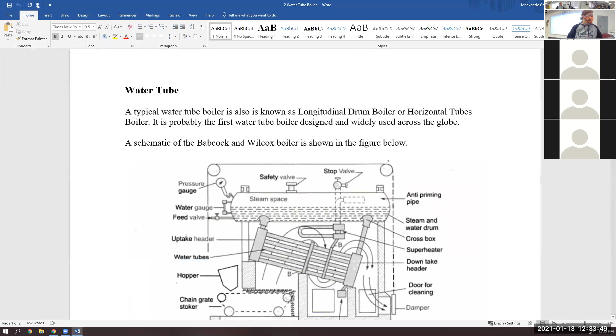So water tube, this one is a B&W. You've got your steam space up here, your water tube, and the flue gas moving through. This mud box, as we circulate water through, after it interacts with that ash, it gets kind of grody, so some of this water doesn't become steam. It has attached particles, called mud, and cycles back down. That can be cleaned and used again, but not 100% of the water going in mixed with that pulverized fuel ends up as steam. That's an important thing to know, that there's a little cycle between the mud drum and the water mixed with our pulverized fuel. That flue gas then heats around our water tubes.